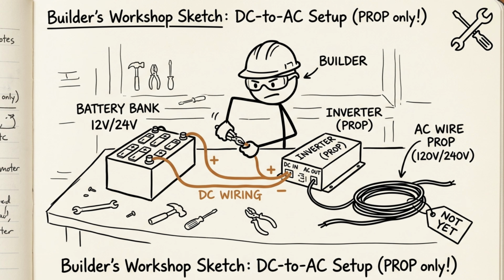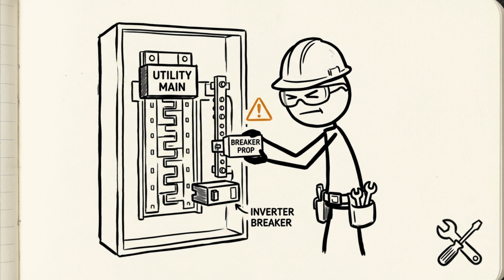Phase 3. Install the battery bank and inverter, and wire the DC side first, fully isolated from any AC connection. Never connect the inverter's AC output to the subpanel before the battery and DC wiring are complete and verified. Phase 4. Run the AC tie-in from the inverter to the transfer switch and subpanel, sized per the 125% continuous current rule, respecting the busbar rule so the combined rating never exceeds the busbar's safe limit.